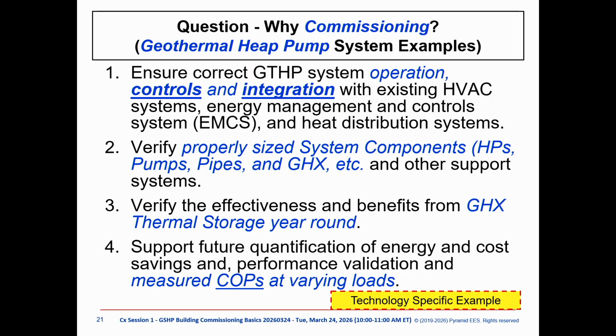Verify the effectiveness and benefits from the ground heat exchanger thermal storage year round. You want to make sure that this temperature is swinging up and down, and it's the same thing for 10 years. Because if it deviates and becomes too cold or too hot over a 5 or 10 year span, that means the ground heat exchanger is going to be ineffective after a while. And then you have to have a cooling tower or a boiler, and that does not become a good story.